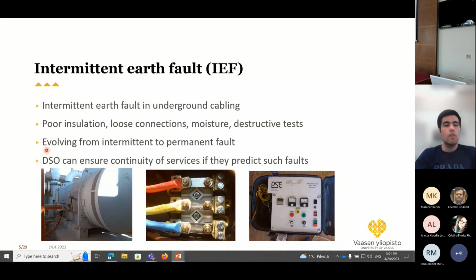And since this type of earth fault can evolve from an intermittent one to a permanent one, if we could predict it, it would be a good idea, and it can benefit the distribution system operator in ensuring continuity of service.